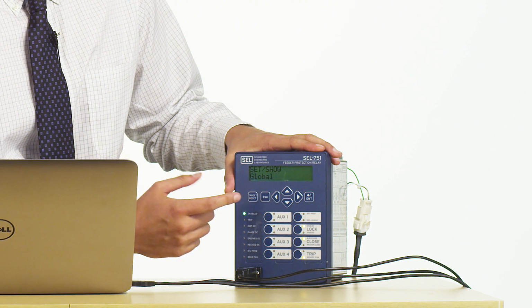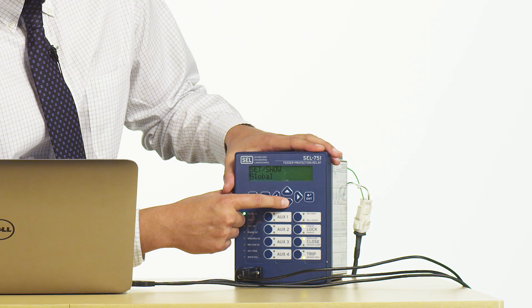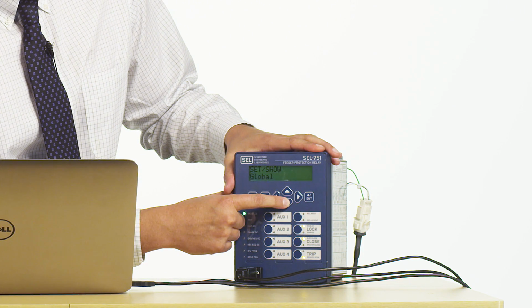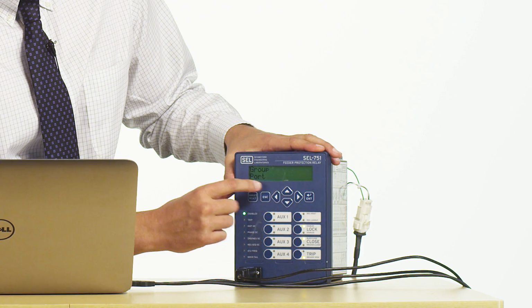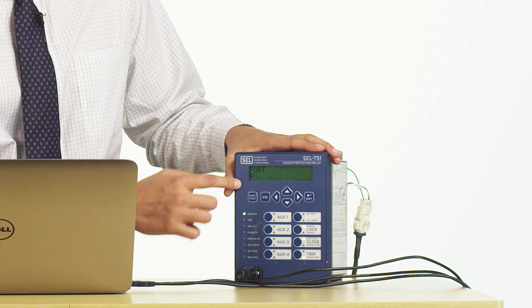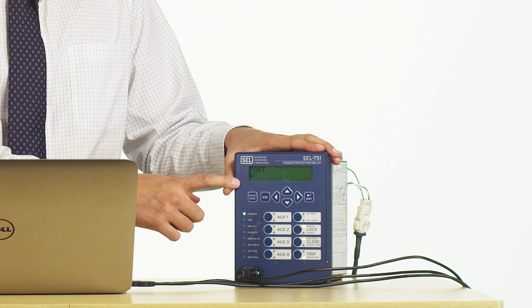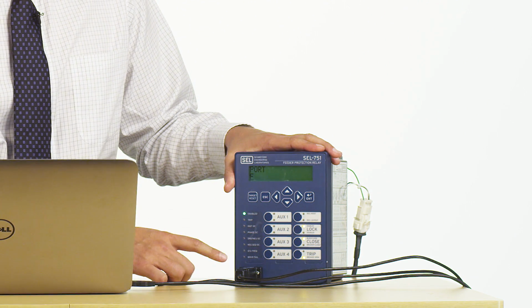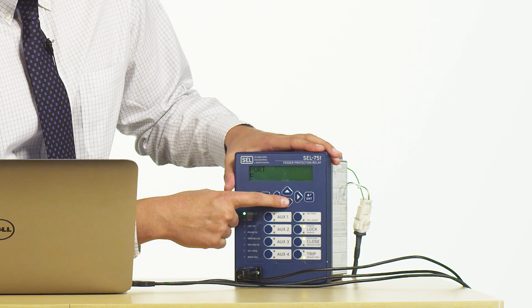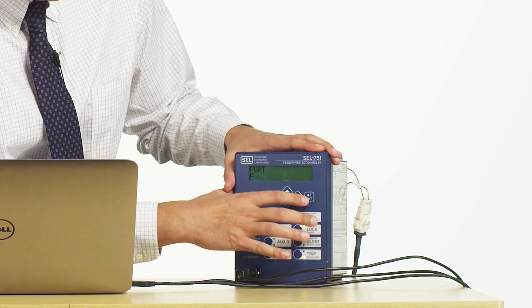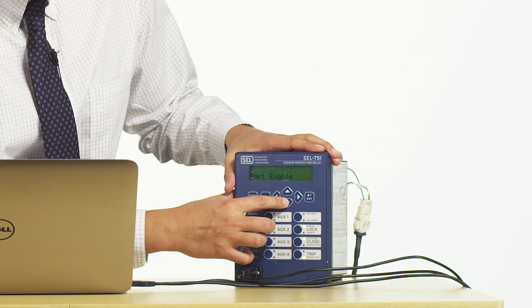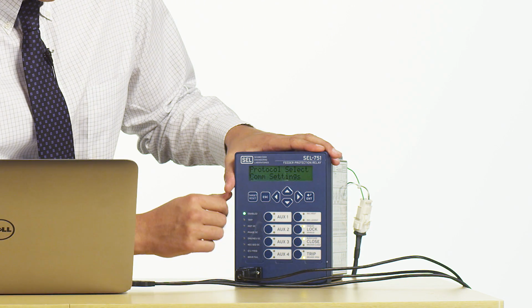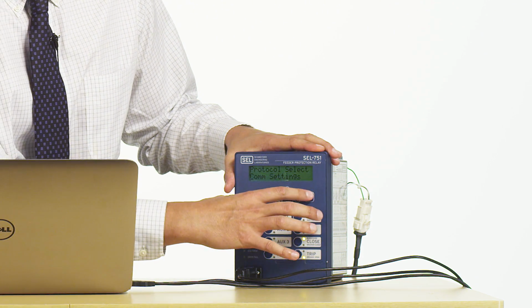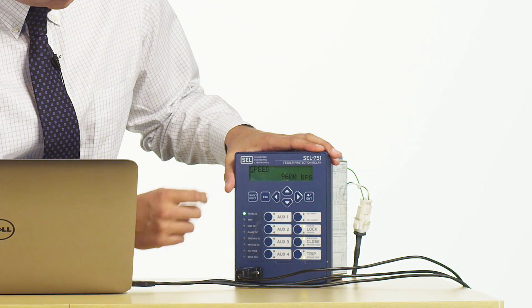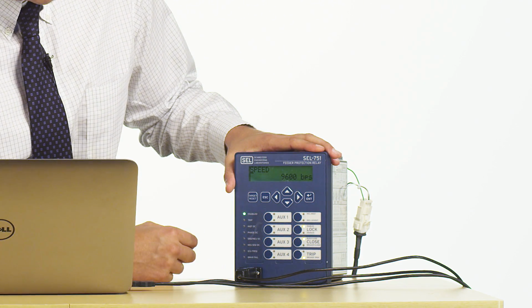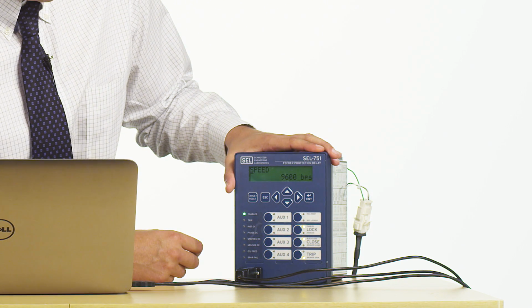Now we're in the submenu structure of the set show, and we will need to navigate to the port and hit enter again. This is going to give us all of the settings of the various ports that the relay has. In particular, since we're connected to the front port, we will want to navigate down to port F, hit enter, and find out what the communication speed of the device is. So navigate down to COM settings and hit enter. And here we see the speed of the front port that we're connected to right now is 9600.